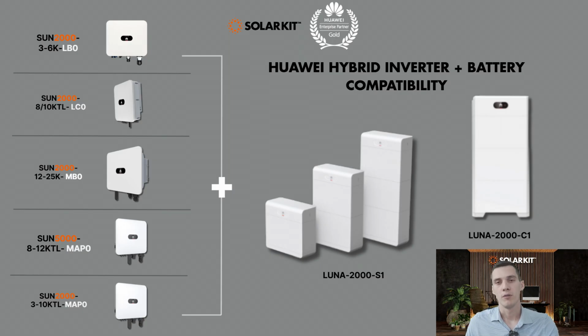Here is a portfolio about the most common residential devices. The first thing you can notice is that the L1 series single-phase inverter is changed to the LB0 series, which has a slightly different power range. Also very important, the LB0 series has the startup voltage halved - previously it was 100 volts, now it's 50. So basically you can start up the inverter with only 2 solar panels installed. As mentioned, you can use any kind of Huawei batteries for that system, so a very small system can already be installed with these inverters and will work as intended. Also worth mentioning, with this reduction in startup voltage, the inverter will start to produce sooner in the morning and function later in the day when the sunshine is not that strong anymore, so basically it extends the working time of the inverter.